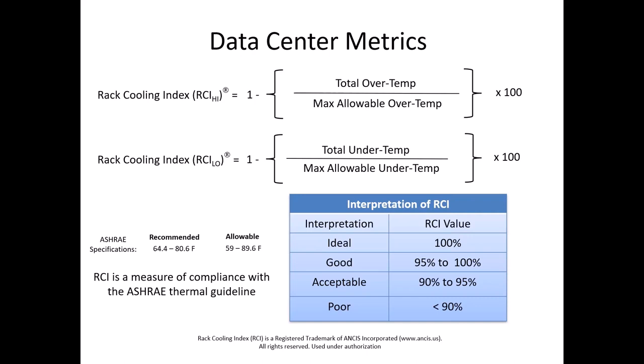That's different, right? There's still just a few points above the recommended, but the difference is that in the second case, they are much above the recommended range. So that's going to give another RCI value. Correct. So it takes into account quantity and magnitude both of these numbers, and that's one of the reasons I always liked it. It gives you in one metric both quantity and magnitude.